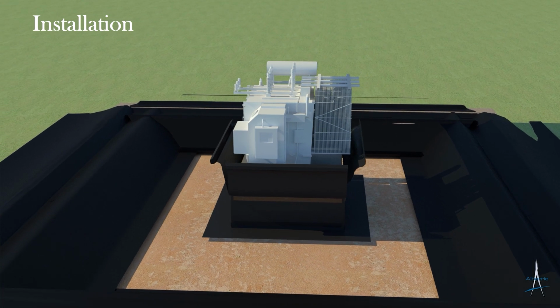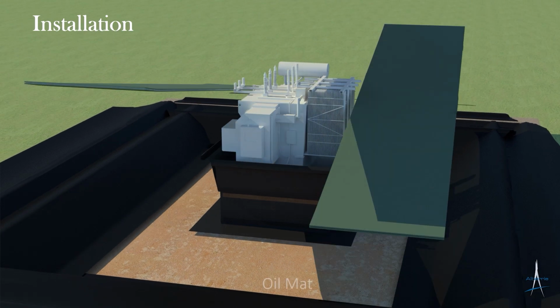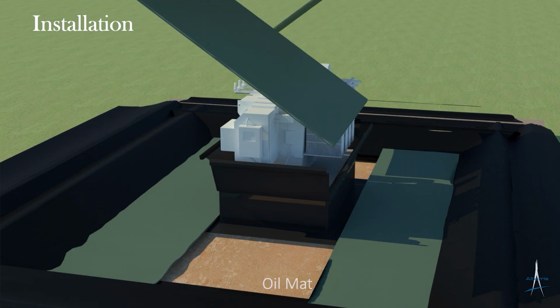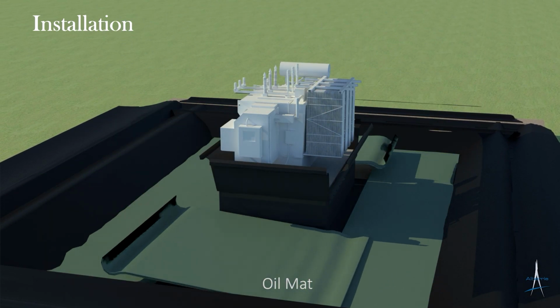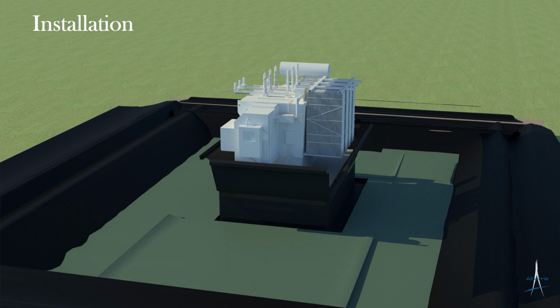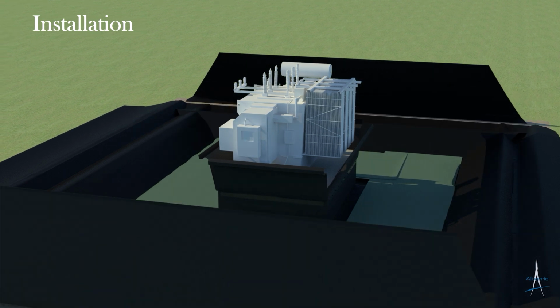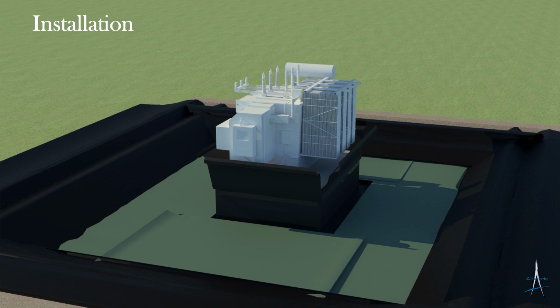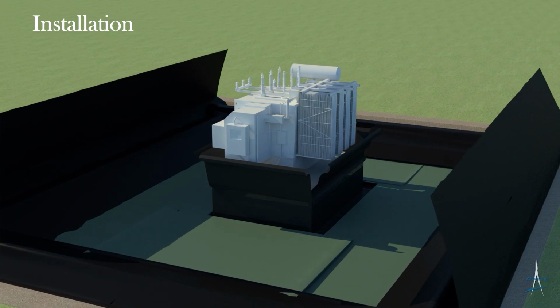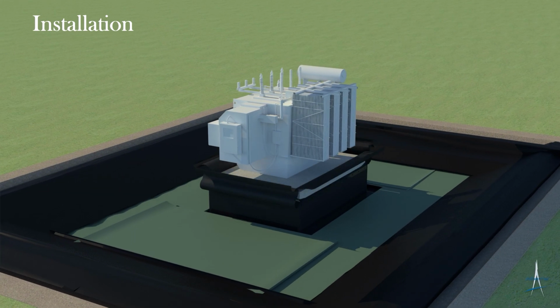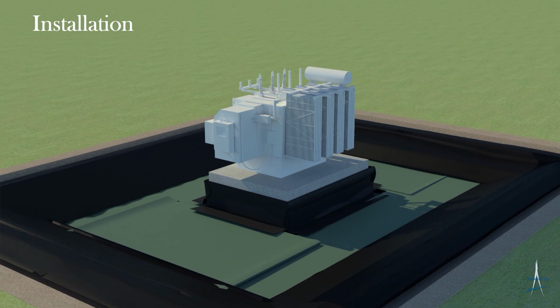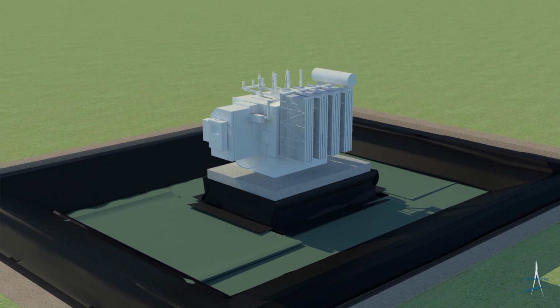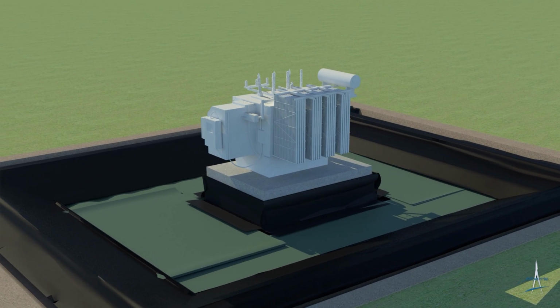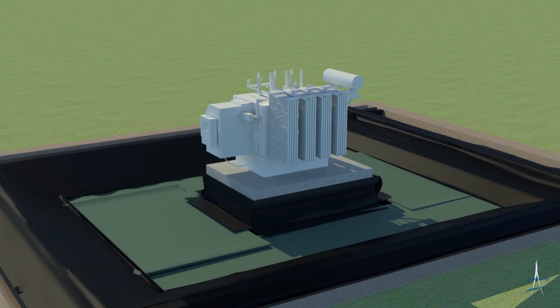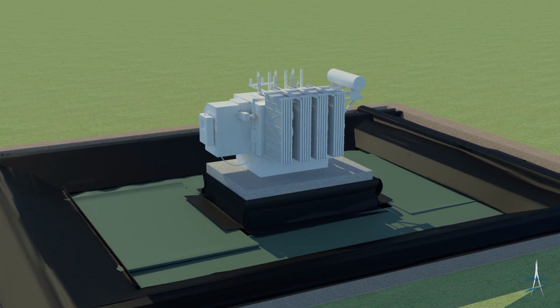Next, smart fabric, or oil mat, is laid out across the bottom of the containment area and secured to the impermeable liner using a specialized sealant adhesive. The excess impermeable liner, both around the transformer pad and the containment perimeter, is now lowered on top of the smart fabric and sealed using the same sealant adhesive. Once this step is completed, the containment is bonded and ready to accept the remaining layers.